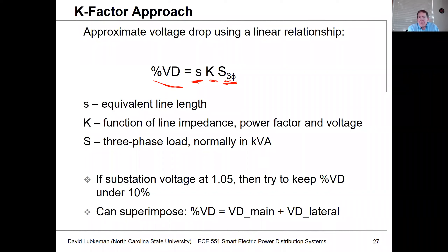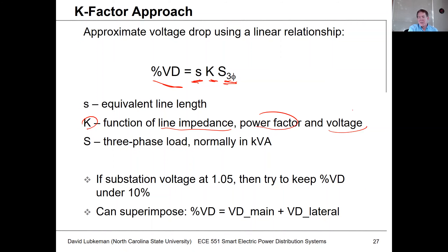If we were going to double the load, we double the voltage drop. This K-factor is a function of the line impedance, a function of the load power factor, and a function of the voltage level that we're working at. We assume the load is going to be balanced, so we're working with three-phase quantities.